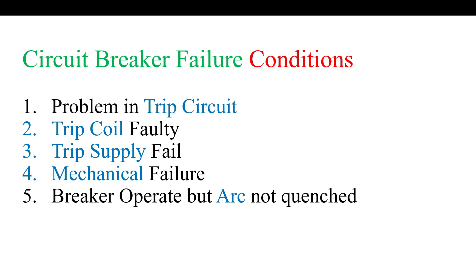The fifth condition, also called a failure condition in literature, is that the breaker operated but the arc was not quenched. This is a very rare case — the breaker operates but the quenching media, for example SF6, oil, or air, is not capable of quenching the arc. Because of the arc, current continues to flow. This is also a breaker failure condition and the CBF relay will operate.